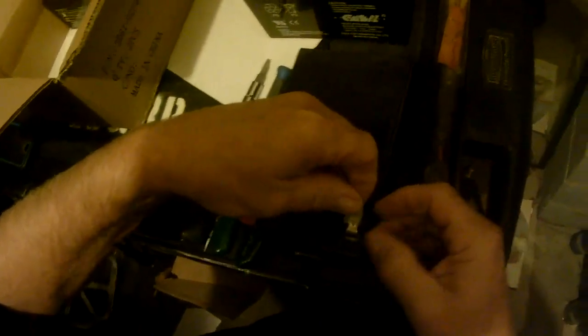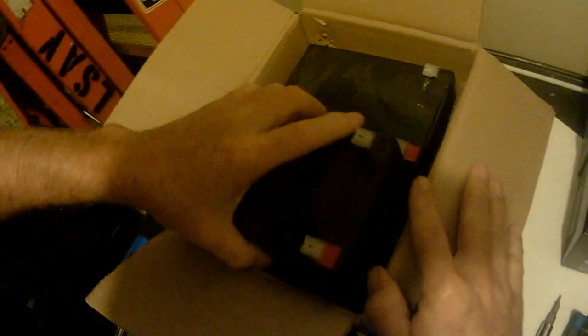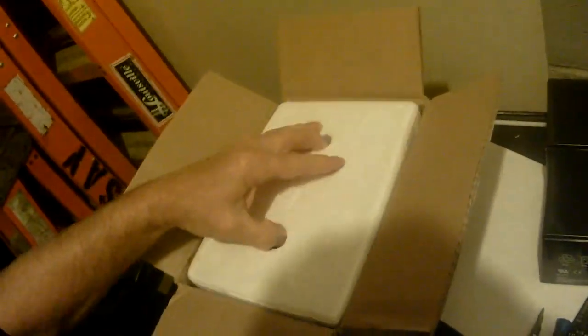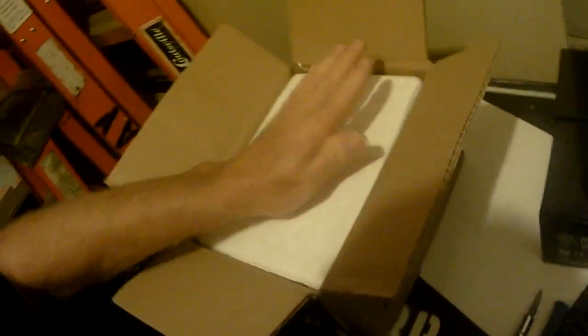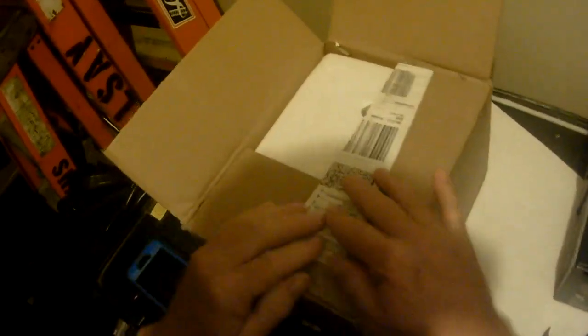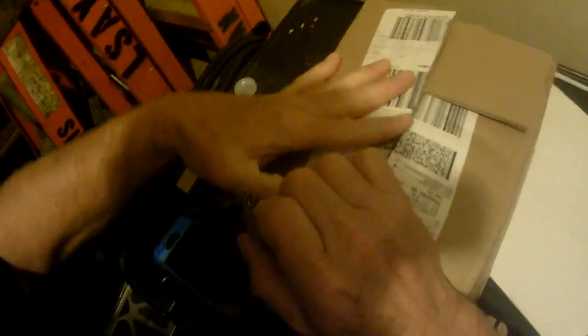If you don't have the little plastic things or if you don't have the box, it'd be a good idea to use some electrical tape and tape up the terminals. There's plenty of safety issues, safety bulletins that came out on batteries rolling around a truck. I'm sure you've all seen the picture of the service truck catching on fire because the batteries rolled around and shorted out on the shelves.